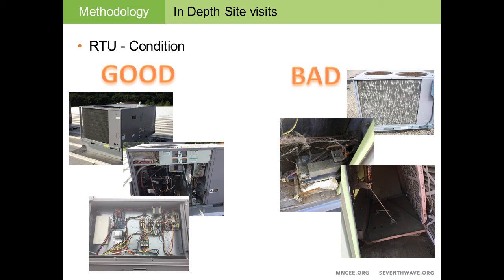On the right side, you get a little bit of an indication of things we saw that were bad. The upper right-hand picture shows an excessive amount of hail damage to the condensers, and the dust that's associated with not maintaining the unit. This is a pretty good indication that not much is happening with regard to maintenance on this particular unit. And the rightmost picture on the lower right shows a damper that's just not functioning very well. If you look very closely, you can also see that there are misapplied filters there. They're overlapping one another. So we saw quite a variety of good and bad in the space.